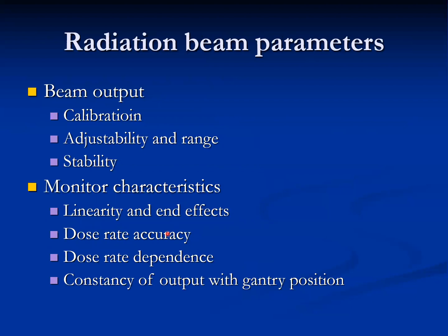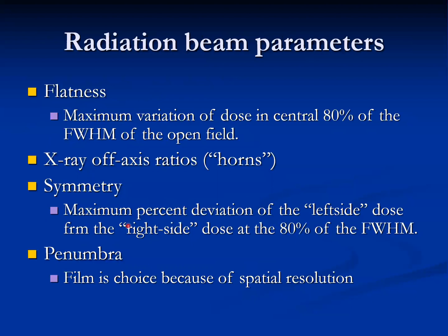Radiation beam parameters include beam output calibration, adjustability, and range stability. Monitor chamber characteristics include linearity and end effect. Dose rate accuracy and dose rate dependence, as well as consistency of output with gantry position, are important to check. Flatness and symmetry are also very important to monitor — flatness being the maximum variation of dose in the central portion of the field, and symmetry being the maximum percent deviation between the left side dose and right side dose at the center of the field.